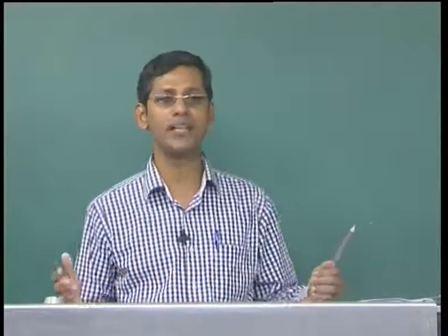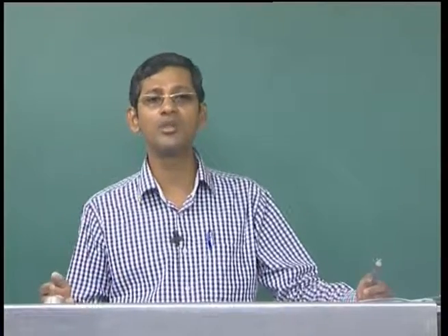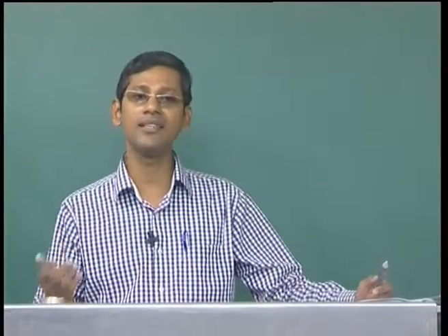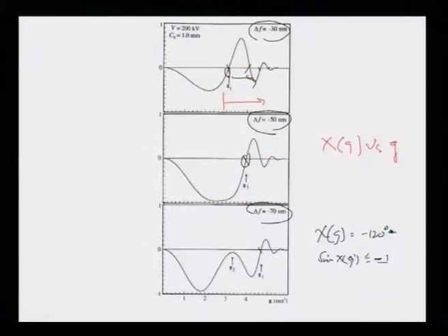The second one is chromatic aberration. Although we can use FEGs, or field emission guns, to reduce the beam energy spread to very low values, it is still very difficult to get zero chromatic aberration, and it is not yet possible to correct chromatic aberration to that level. So, because of the presence of both chromatic aberration and spatial coherency problems, these frequencies can never actually be used to get information from the sample.